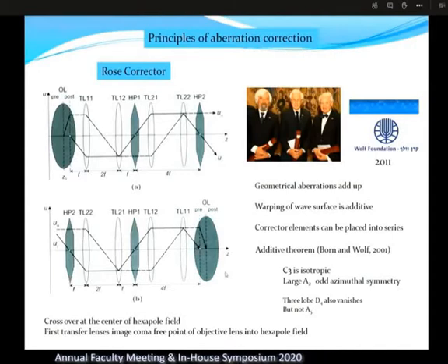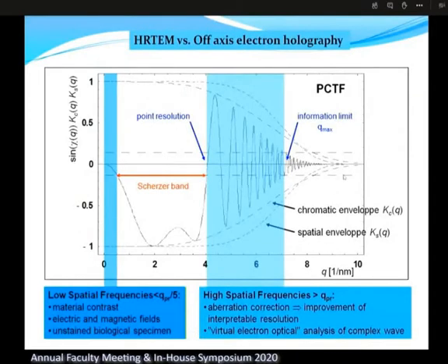in this field. So here's a brief comparison between off-axis and inline holography of the HRTEM. Your HRTEM basically acts as a band pass filter. So it only transfers information with high contrast only for a specific frequency range, and that we basically align to the interatomic spacings. And holography can actually transfer all frequency range information.